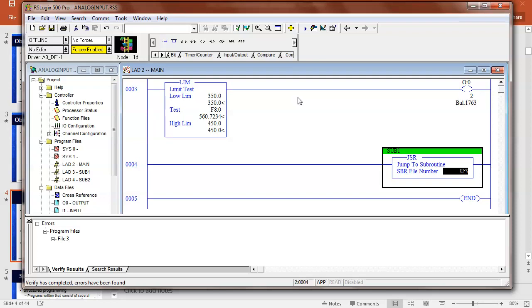This is what? This is the file number, the program number. So this is the program I'm going to. So I'm saying go to what? 3. So every time this program ran, when it hit this, this would be what we call an unconditional subroutine, which means what? No input. If I wanted to make it conditional, I would put input. Could be compare instructions, like if this number is this, then run the subroutine. That makes sense.